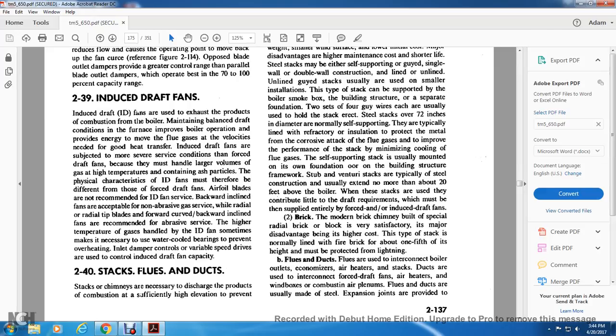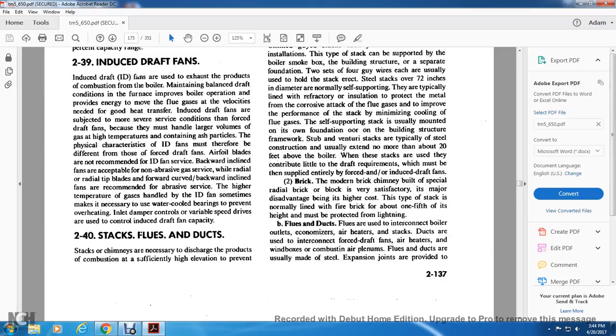Physical characteristics of ID fans must therefore differ from those of forced draft fans. Airfoil blades are not recommended for ID fan service. Backward inclined fans are acceptable for non-abrasive gas service, while radial or radial tip blades, forward curved or backward inclined fans are recommended for abrasive service. The higher temperature of the gas handled by the ID fan sometimes makes it necessary to use water-cooled bearings to prevent overheating, and inlet dampers and variable speed drives are used to control the induced draft fan capacity.